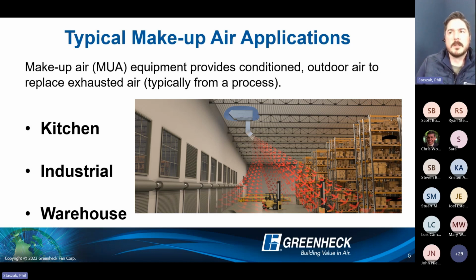Again, we'll focus on this a little more toward the end of the presentation, but there are a couple of different approaches here. Heavily favoring direct gas-fired heat, superheating that outside air, 0 degrees entering, 140 degrees leaving air temperature, to effectively do two things. We're bringing in fresh air when the unit is energized to satisfy a space condition, and we're going to superheat it to typically 140 degrees, satisfy the space condition, and then disable.